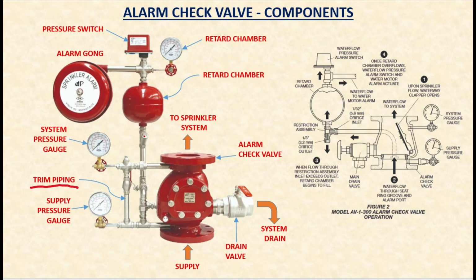So the first thing is the main valve body. See this one. The main valve body is basically a check valve or a non-return valve. The alarm check valve allows water to flow only in one direction, from supply to sprinkler heads. That means water can flow only from the supply to the sprinkler system here. So this alarm check valve prevents backflow into the water supply system. That means water cannot flow back.